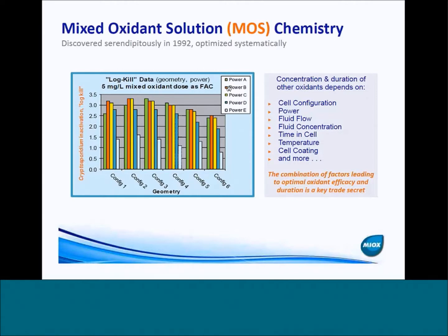The legend here talks about different cell set points. Power is an important component of what the cell set point is, but there are other factors that are extremely important as well. You can see it going all the way from set point A all the way to power E. If you take a cell configuration, say configuration six, you can go from what would be kind of a sodium hypochlorite disinfection efficacy at a little over half a log inactivation up to at least an order and a half of magnitude difference by changing the set points for that electrolytic cell.